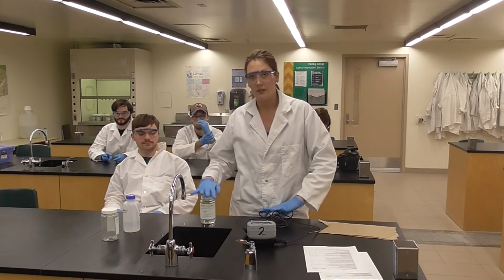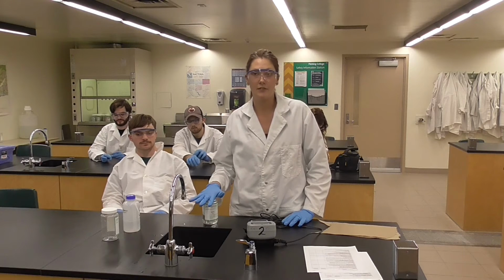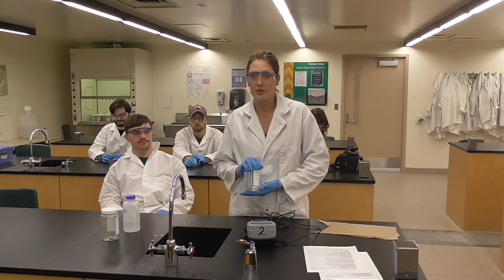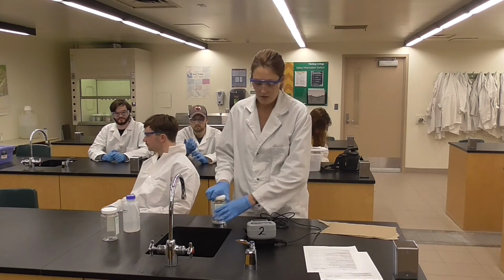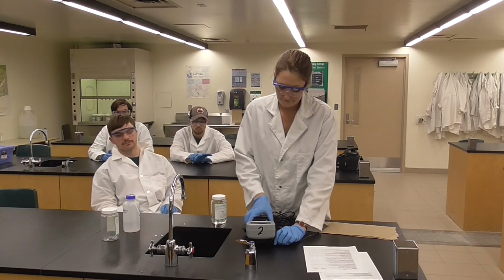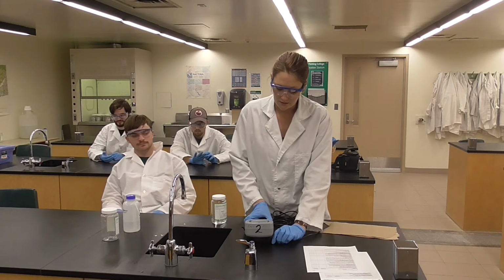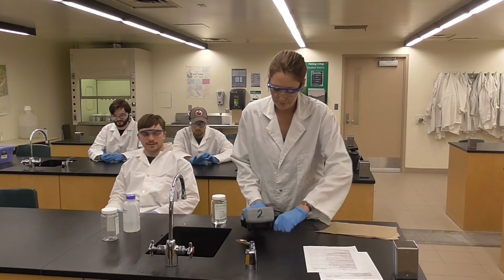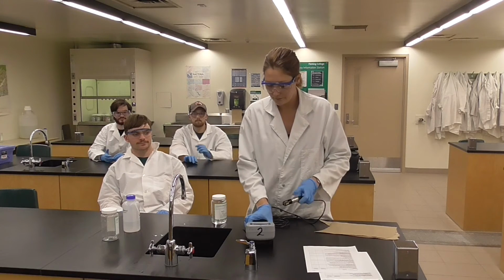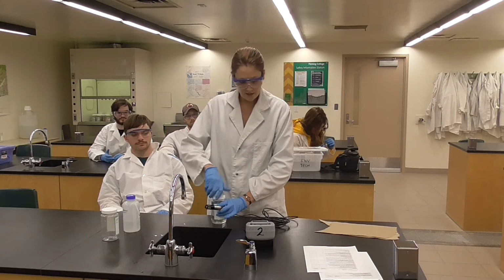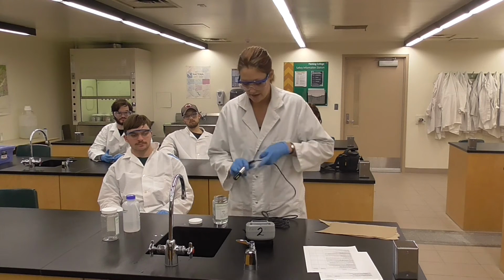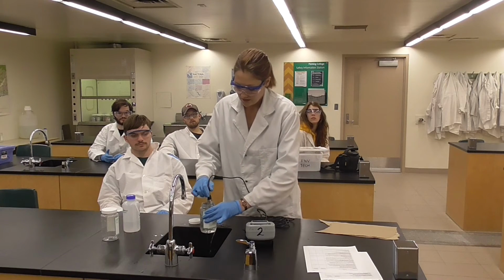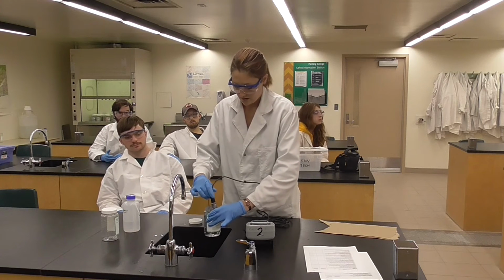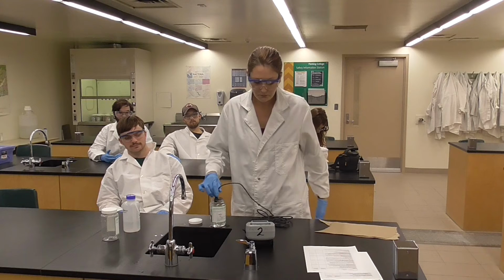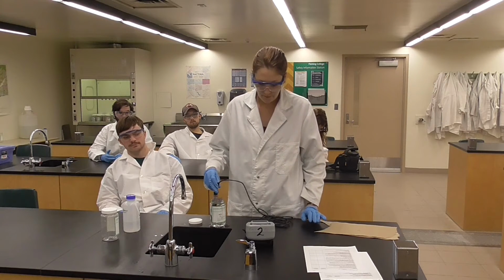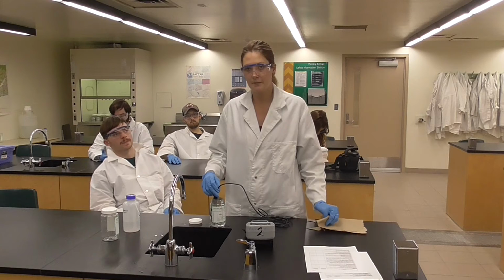So this, as we said, Will has already tested and has established that there is 11 milligrams per liter concentration of dissolved oxygen. So we're now going to turn our machine on and let it run its little setup here. So that's all good. Let's back up. And so when I put this in here, it needs to be stirred around at a rate of 16 centimeters per second. So we're just going to set that there, make a bit of a mess, and just let that run until the readings here can stabilize.